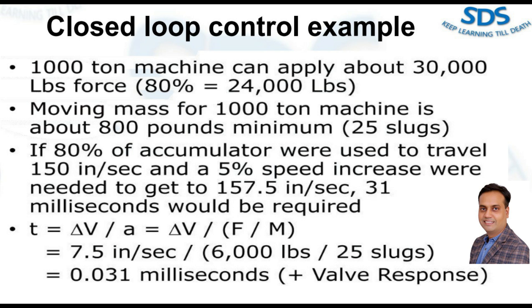Now let's consider a scenario when the machine is operating at 80% accumulator usage and traveling at a speed of 150 inches per second. Suppose a 5% speed increase is required to reach the target speed of 157.5 inches per second.